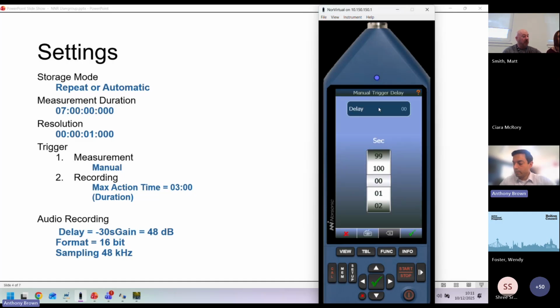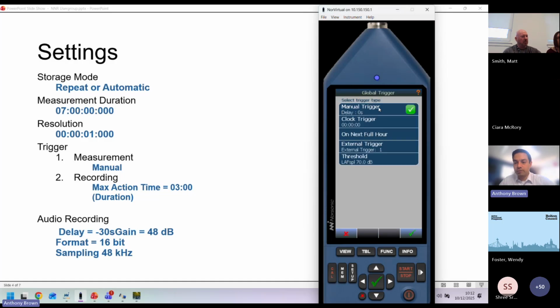What you can do is set a delay if you want. The idea is that when you press the start button, it will count down from this number. So if I press start, it would go 3, 2, 1, and then start measuring, or you can just leave it at 0. Just make sure right now that you set it to manual trigger. Do not set it to clock or any of these other settings at the bottom here. This global trigger just controls how the start button works.